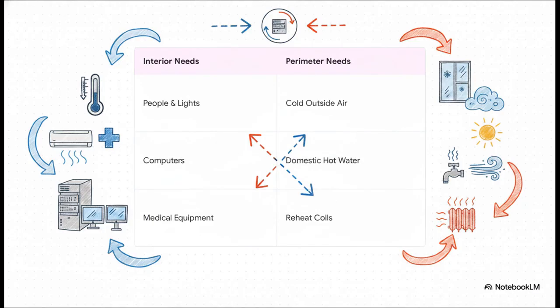To really appreciate this solution, we first need to look at the invisible conflict that's happening inside modern commercial buildings every single day. It's kind of like a giant tug of war. On one end, you have interior needs. These are spaces that require constant cooling because they're packed with people, lights, servers, or heavy medical equipment. But on the other end, the perimeter of the building desperately needs heating to fight off the cold outside air. Plus, you need domestic hot water and reheat coils.